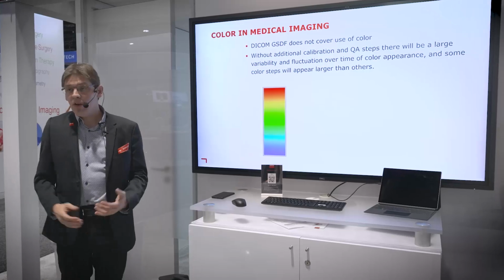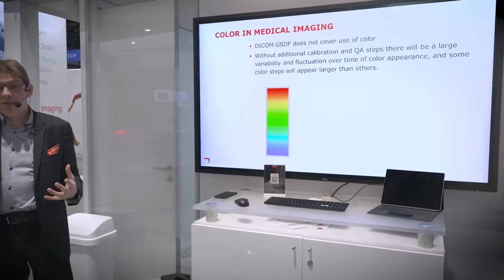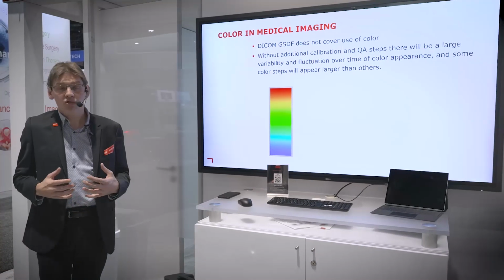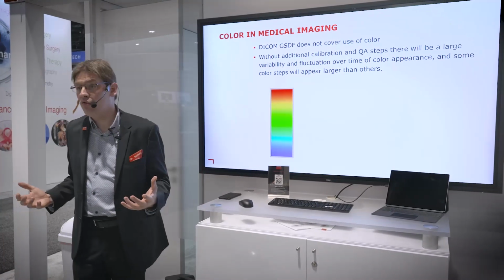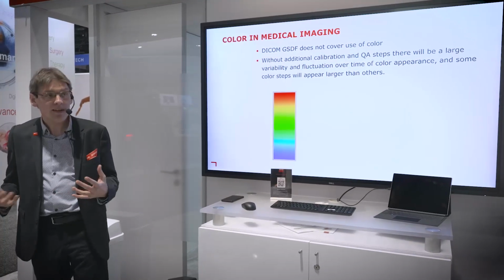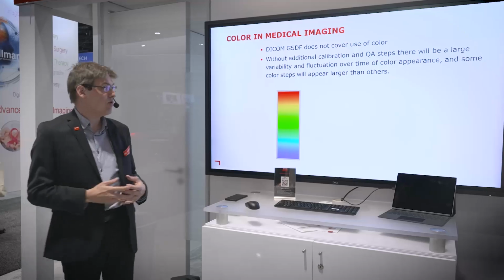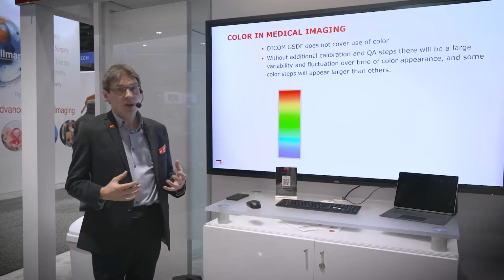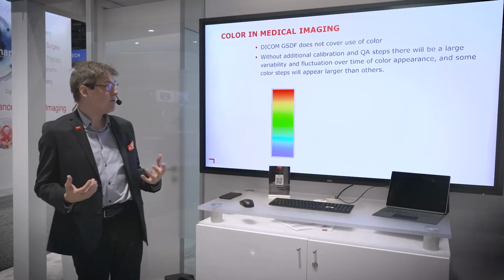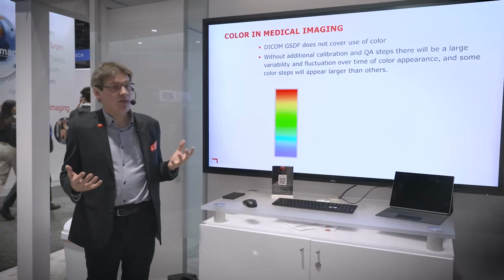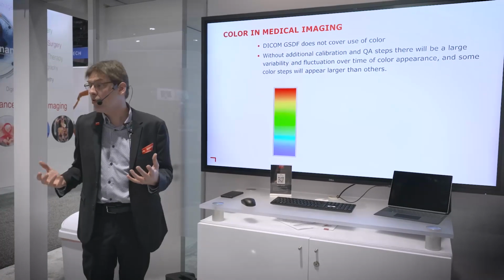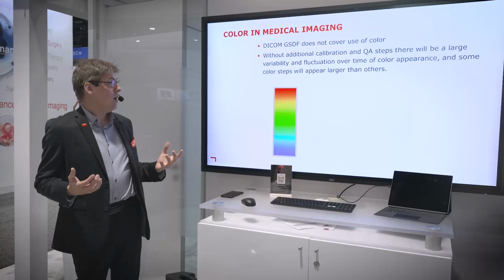So, what about calibration? Everybody knows DICOM calibration, DICOM GSDF calibration. Well, this does actually not cover color. So, DICOM is not at all going to do anything on calibrating or safeguarding consistency of color appearance. So, if you don't take any additional steps, then if you just calibrate the display to DICOM, you will still have a large variability and fluctuation of the color characteristics.